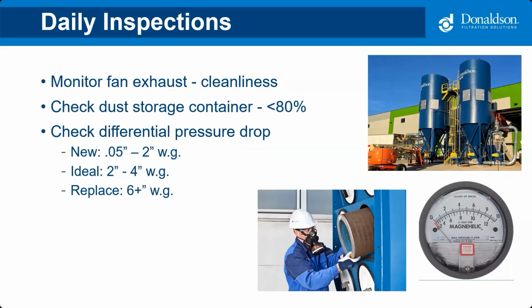We recommend that you change it at 80% just to give you a safety factor there. You definitely don't want to wait until it fills up into the hopper or the collector. Not only is your maintenance team going to be really upset because they're going to have a heck of a mess to clean up when they ultimately do replace it or empty it, but getting dust up into the hopper of the collector, now that dust isn't getting removed and it's blowing around inside the collector, it's reintroducing more dust, and it's going to cost you filter life.